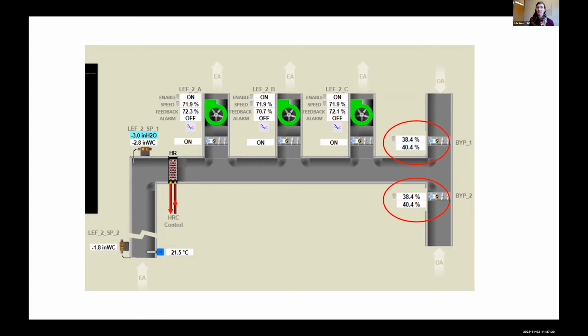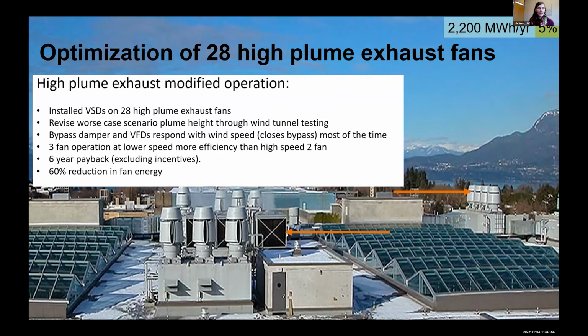At the same time, originally we would have 2 of these exhaust fans running. They're duty standby. There's one fan that's always there for redundancy, and at the beginning only 2 of the 3 fans would run, and it's actually more efficient to have all 3 fans run at the same time at a lower speed on the fan curve than have 2 of the fans run at a higher speed. And so this is a project that we implemented at Life Science Center, but on a number of systems on campus, and had a 6-year payback for this project in particular, and roughly a 60% reduction in fan energy, saving roughly 5% of the building's energy use.